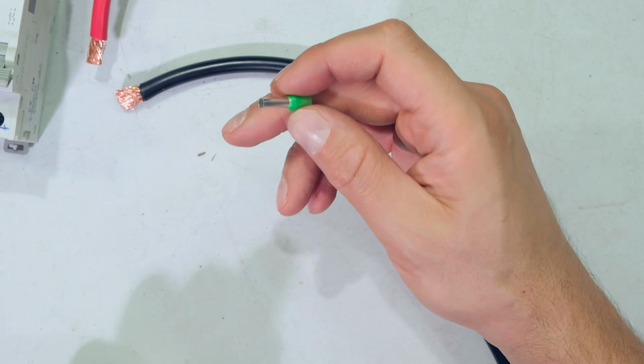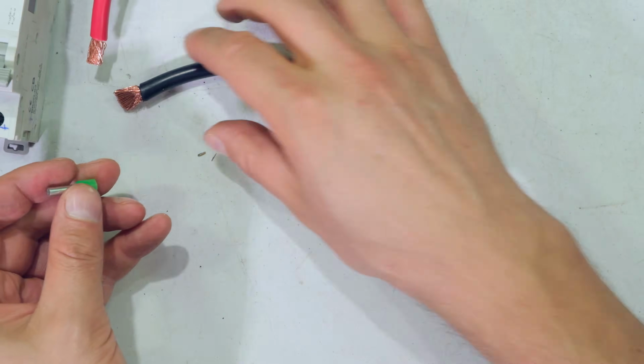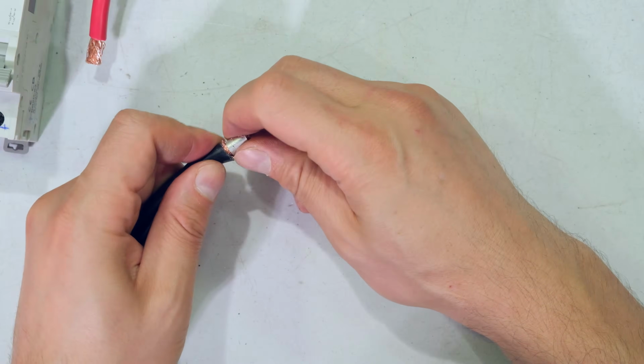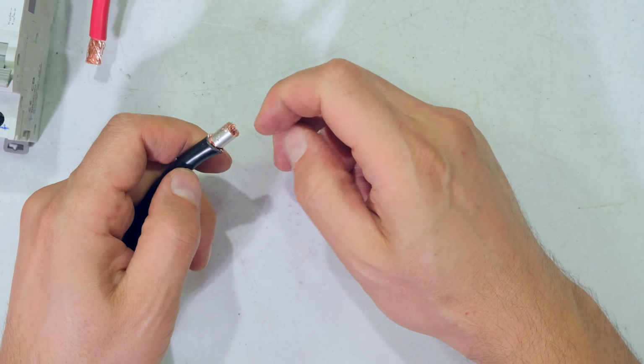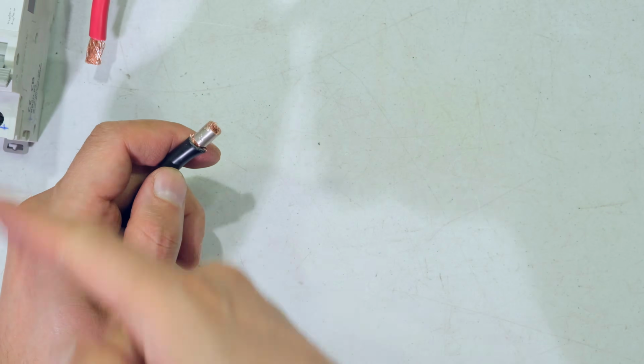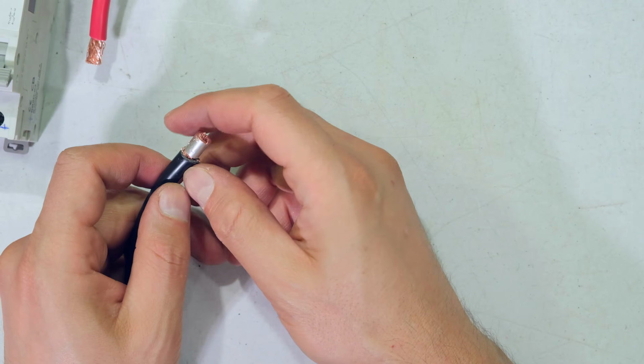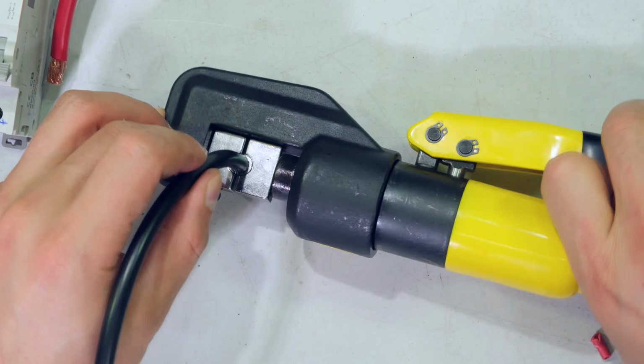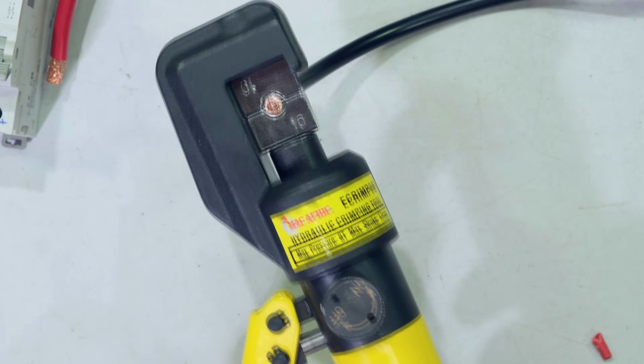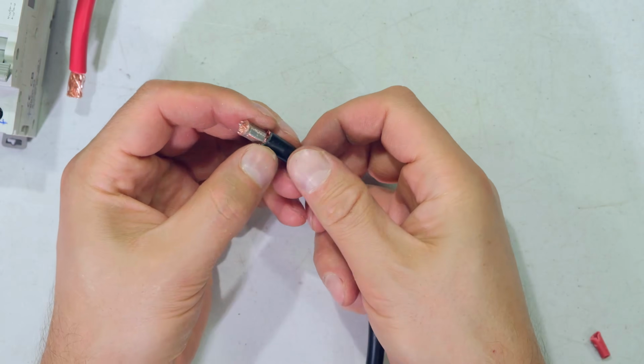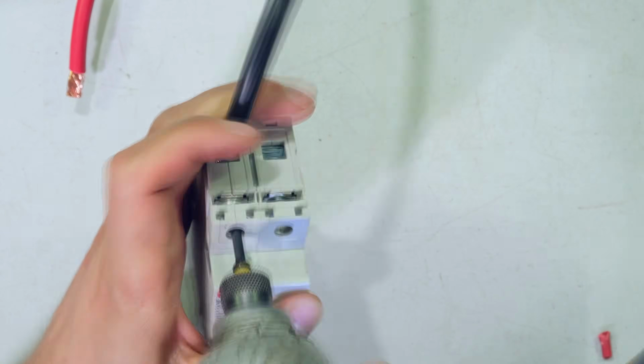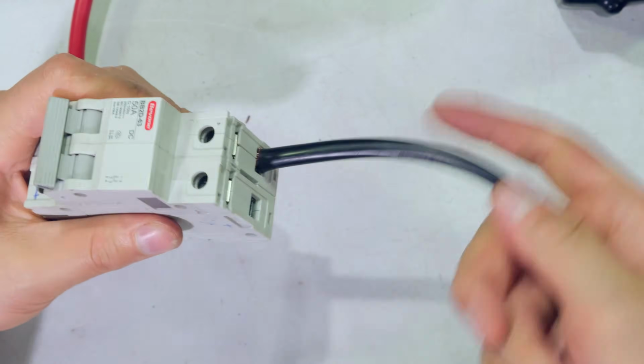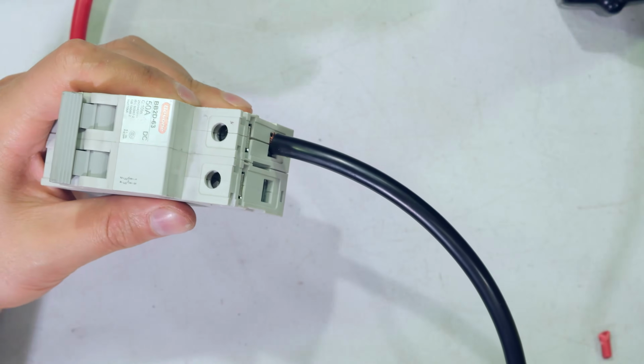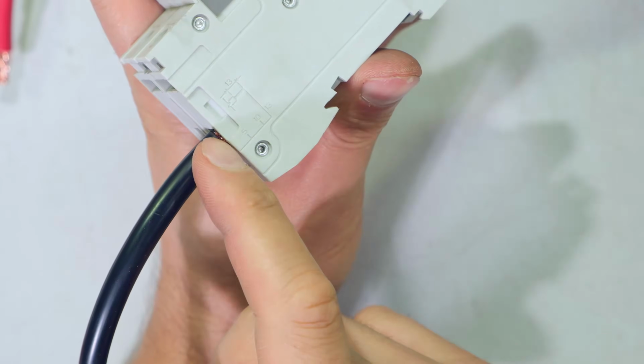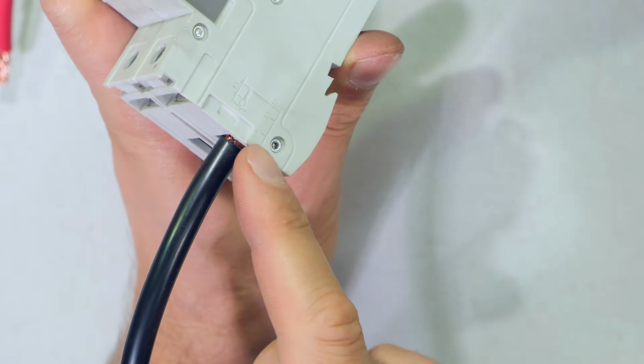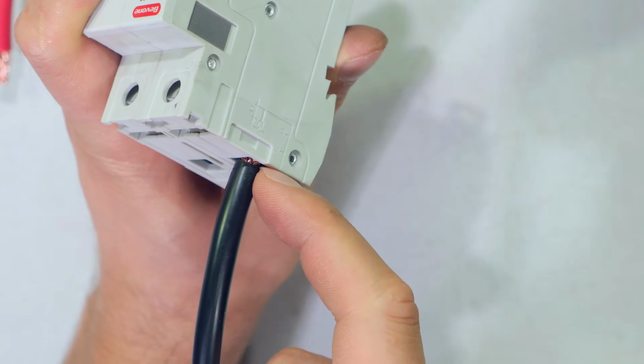So what I want to use is a bootlace, but I don't have one big enough, so it would go like that. So I'm just putting a ferrule around mine, and I'm going to crimp it, and then I'll put that in there. If you've got a spade connector, that will also be perfect. Right, so now I can put this in the circuit breaker. And now, even though I move this, none of the strands are coming out of that terminal. Very important, notice that the jacket is not going inside the circuit breaker, it's just the wires.